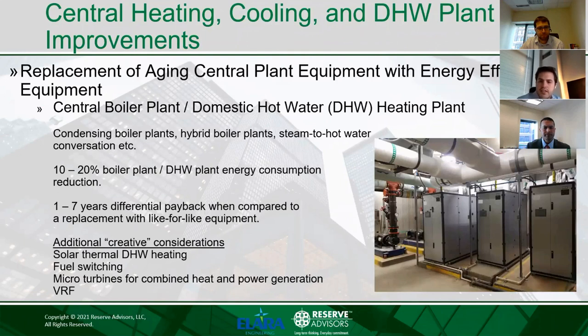So let's start with central heating and domestic hot water heating plants. Central heating plants typically produce hot water or steam for space heating using hot water boilers or steam boilers. Central domestic hot water plants produce hot water for the building's plumbing fixtures, on the other hand, and these central plant projects, as I mentioned earlier, are more suitable for older buildings where aging central plants require replacement. When central heating or domestic hot water plants are scheduled for replacement, higher efficiency equipment should be considered.